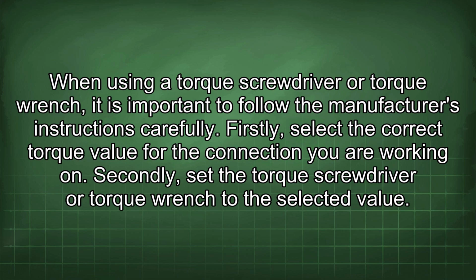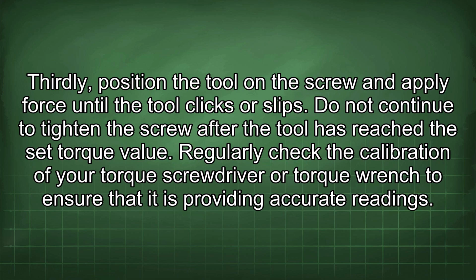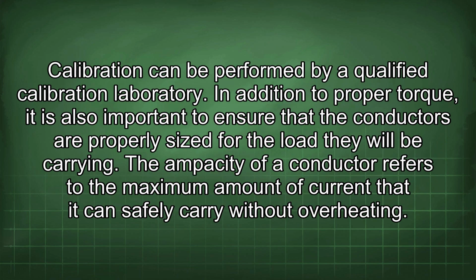carefully. Firstly, select the correct torque value for the connection you are working on. Secondly, set the torque screwdriver or torque wrench to the selected value. Thirdly, position the tool on the screw and apply force until the tool clicks or slips. Do not continue to tighten the screw after the tool has reached the set torque value. Regularly check the calibration of your torque screwdriver or torque wrench to ensure that it is providing accurate readings. Calibration can be performed by a qualified calibration laboratory.